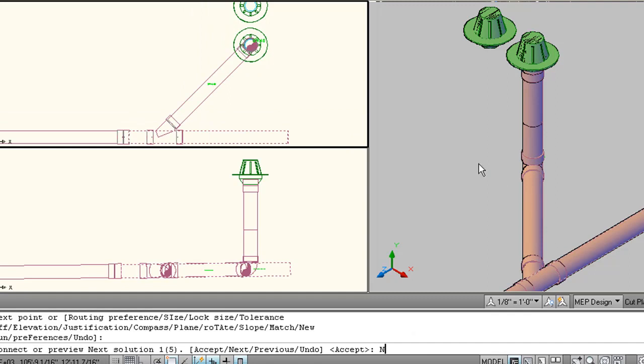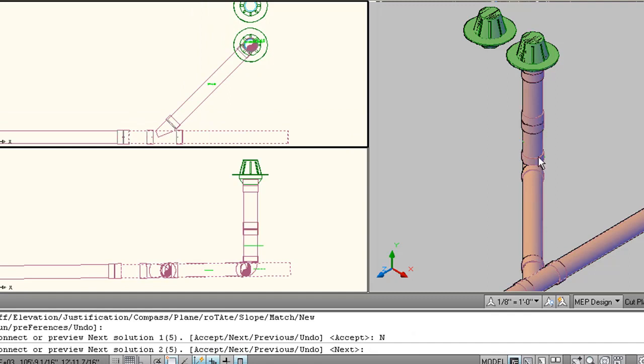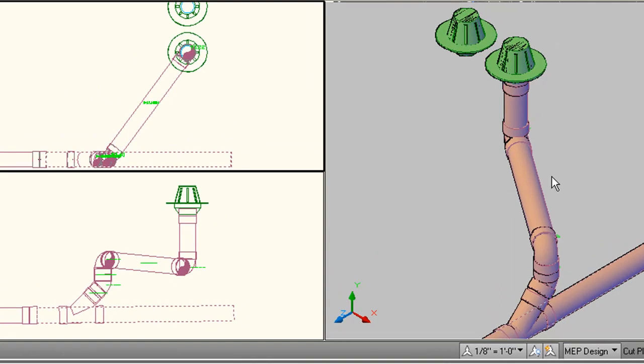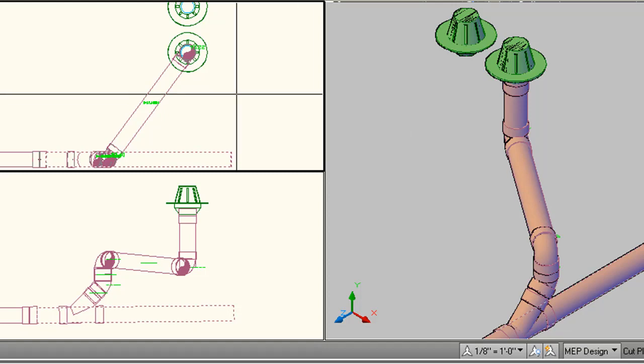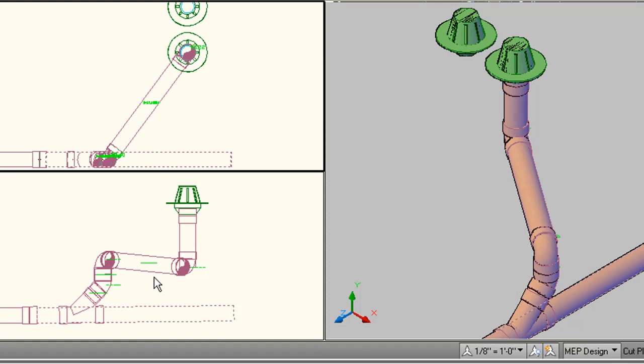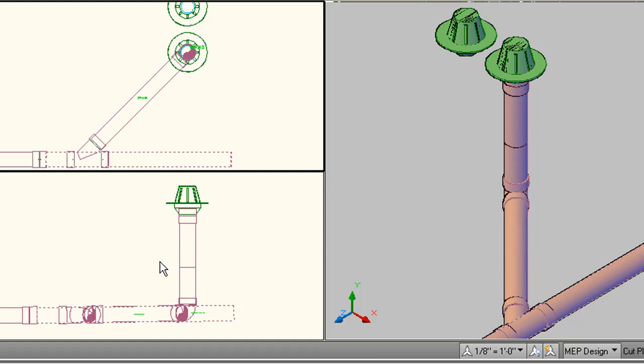So then I would come back and instead of coming in at 90, we'll come in at 45. Again, get near the pipe and hit it, and this is the behavior we're getting. And to show you some of the routing options, there's next, added a coupling, next, lifted the lateral up. And is this acceptable? Is this good? Yeah, you might say this is good. If we want to stay close to structure, that'd be fine. It looks good here. It looks good in plan as well. But remember, in the last video, we said open up an extra viewport. And this is why, because in elevation, it becomes readily apparent this is not a viable solution because I'd have a backward slope. So this isn't going to work.